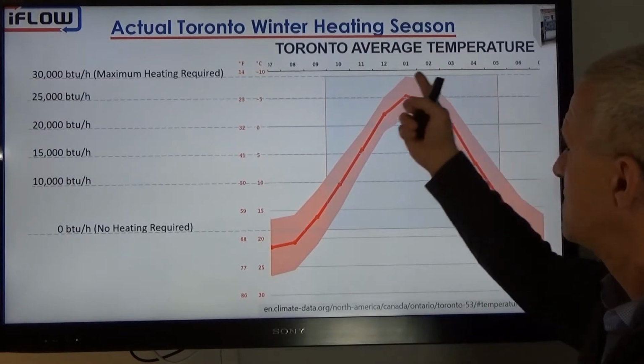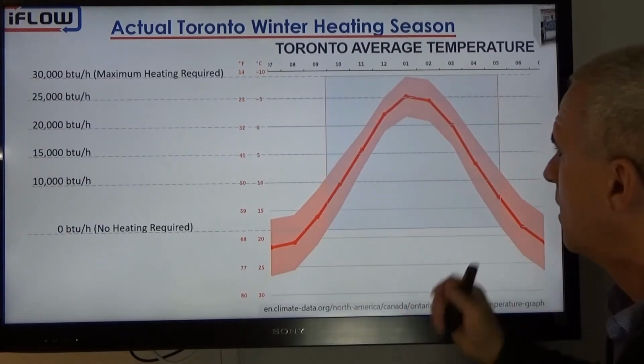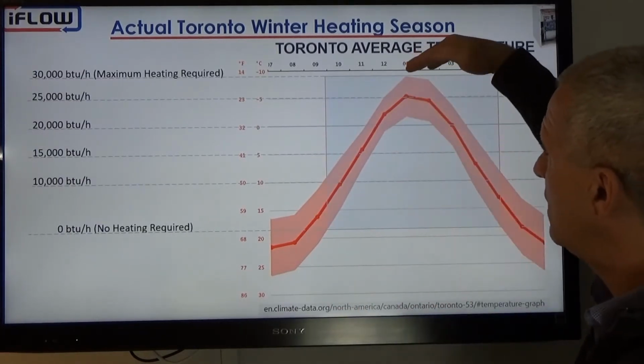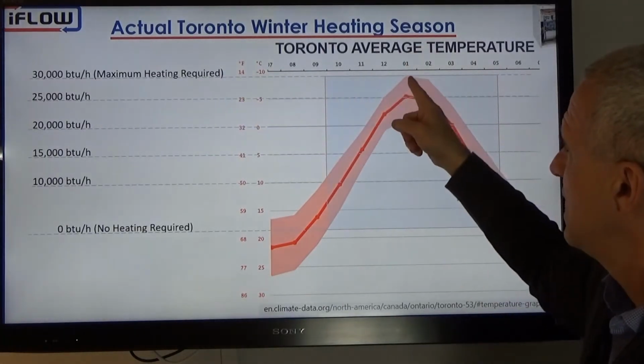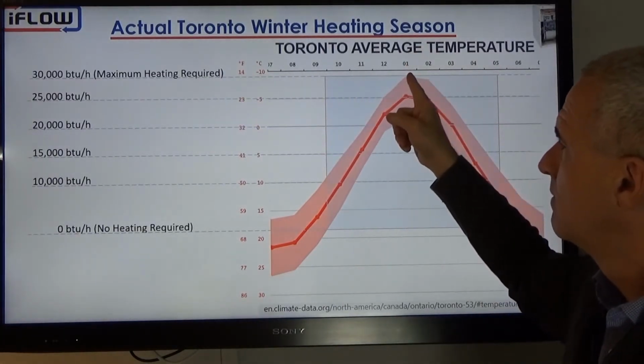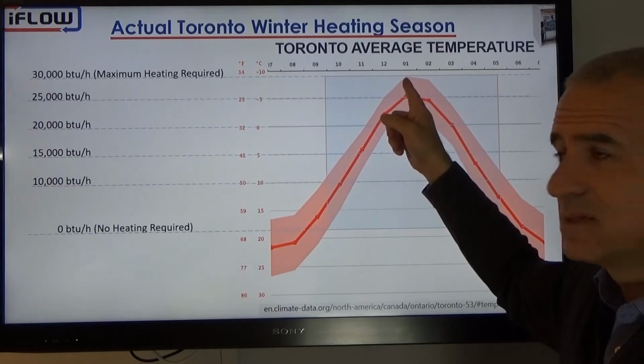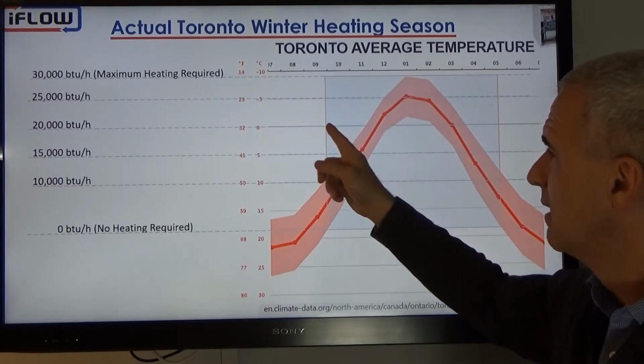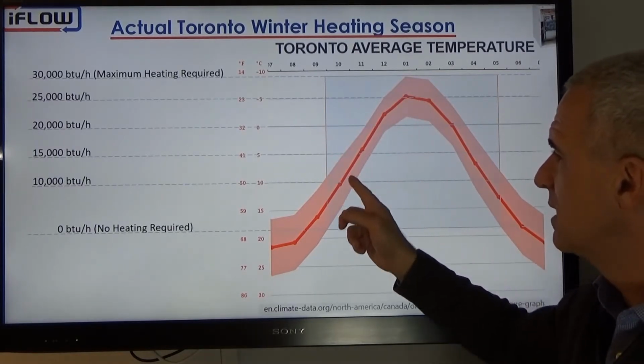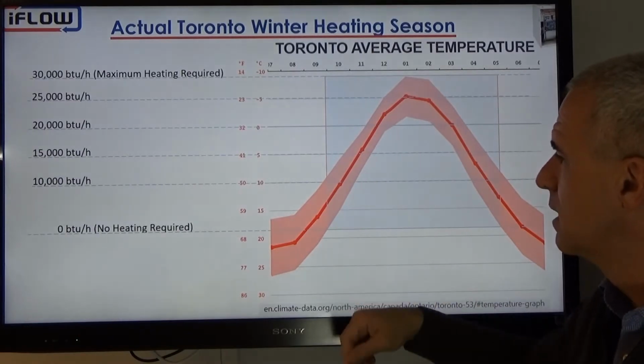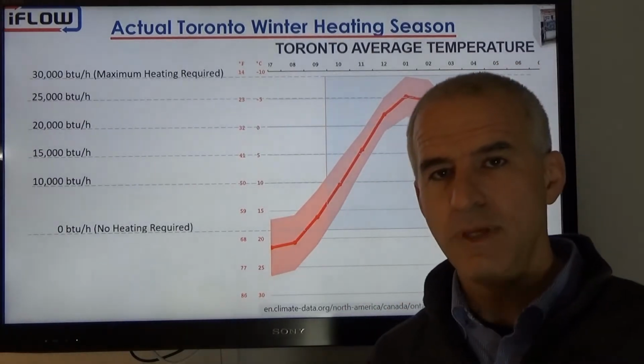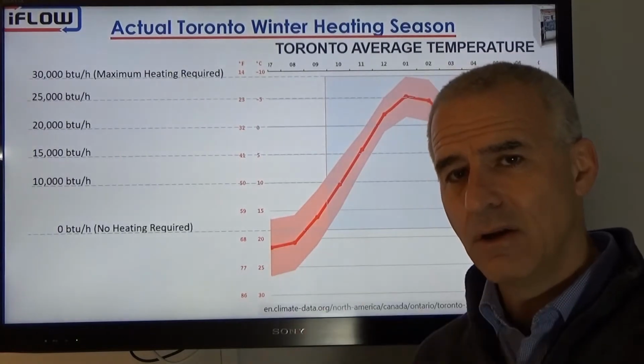The heating season is identified in this blue square, but all to say we need that 30,000 BTUs in the worst day of January and February. But most of the rest of the time we need much, much less than that. 20,000 BTUs, 15,000 BTUs, 10,000 BTUs. So we need equipment that's going to be able to operate at all of those levels.